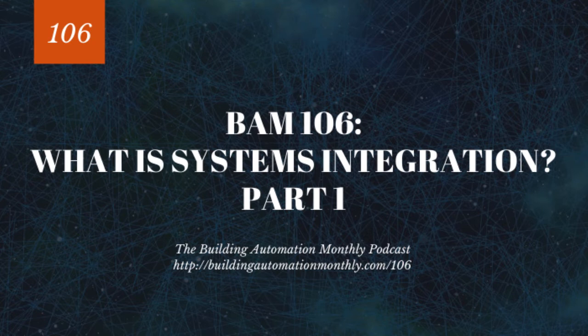So in the case of a BAS device, you may have an advanced application controller that has an object called analog input, and that analog input has a property of present value, of name, default description, priority array, all sorts of stuff. So that's number one, right? I'm just going to do these three things real quick. You have to understand the nuances of the protocol.